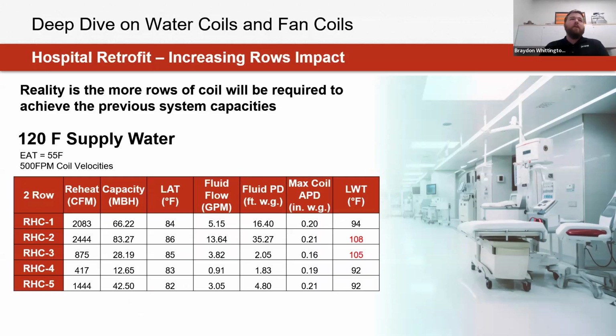The next one, of what Heidi even alluded to, is the reality that we're having to look at potentially increasing the amount of rows of coil. So if we were to still try to achieve that same 20-degree delta of that low water temp leaving that coil, and bump these instead up to a 2-row coil, what we're going to see on that same schedule is good. 3 of these coils now are able to achieve those targets. But a few things we're also going to notice here is a little bit higher fluid pressure drop than was initially set up for that schedule. Initially, they were targeting less than 5 feet of water gauge. Now we're seeing a little bit above 10 feet for that coil itself.